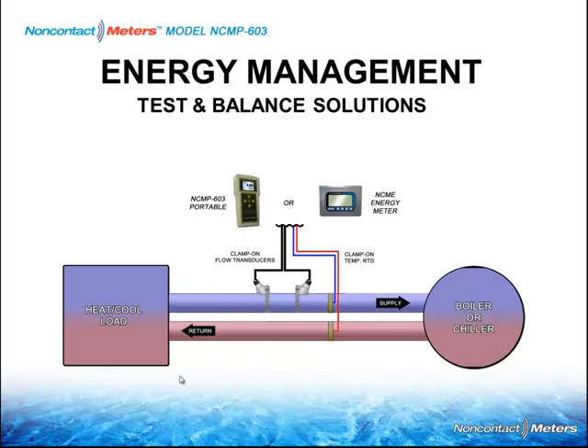Coming in the future, of course, Noncontact Meters is infamous for their dedicated transit time flow meters and energy meters. The portable meter we're talking about today is in the design stage, so in the future you'll be able to take the output of this device to also tie it into a BTU system. To monitor BTU, you'd basically take the flow meter itself to monitor flow on the supply line, and then monitor two temperatures, one on the supply and one on the return line, and collect all that data to give you a BTU calculation. So it's available already with the NCME series, to be available with the portable device in the near future.